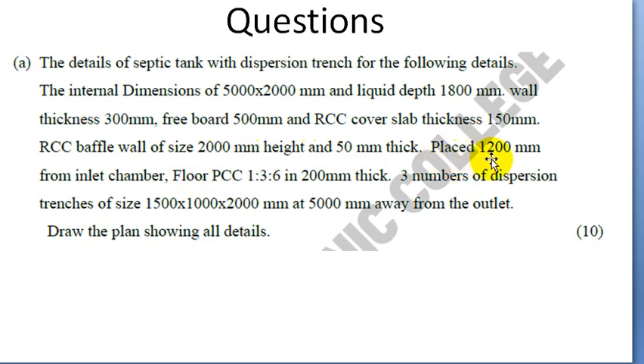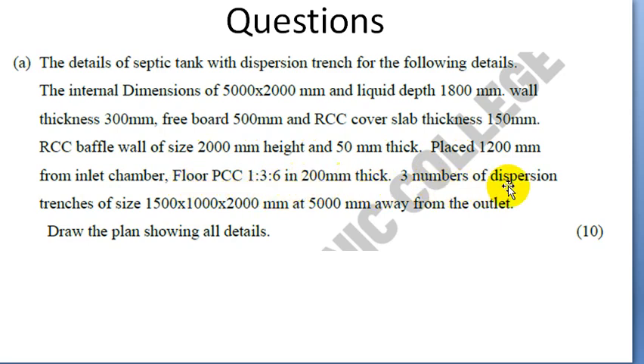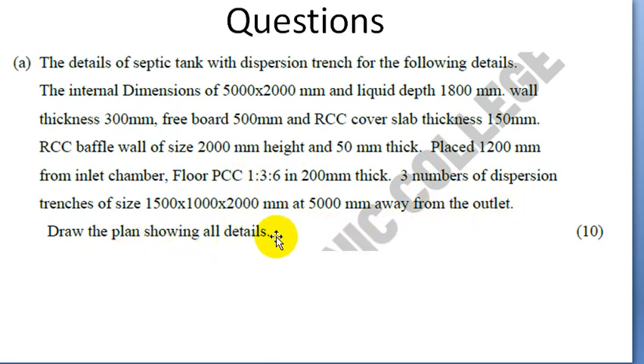The baffle wall is placed 1200 mm from the inlet chamber. Floor PCC mix 1-3-6 is 200 mm thick. There are 3 numbers of dispersion trenches. Draw the plan showing all details.